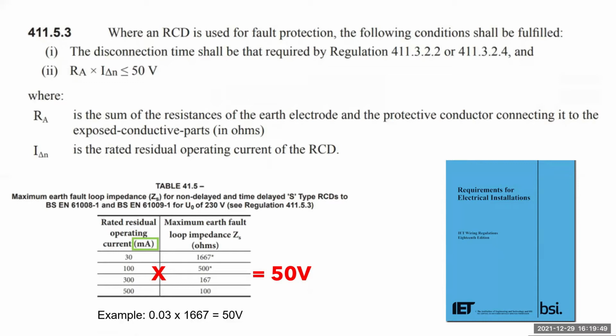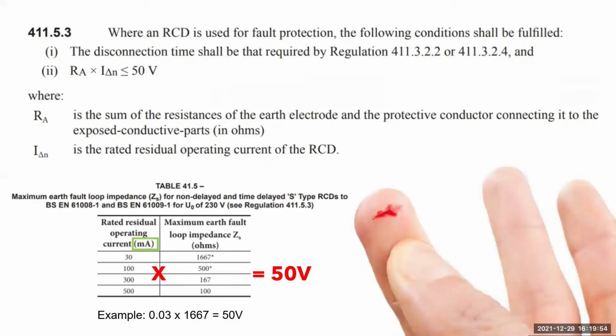It's also worth noting that if your skin is wet or you have a cut, then that touch voltage can be dramatically reduced as the barrier your skin provides is no longer intact, so it could take less voltage to break through the impedance of the skin.